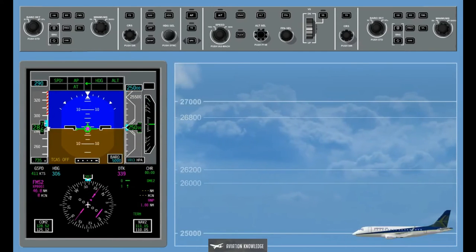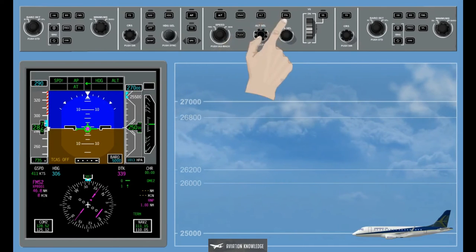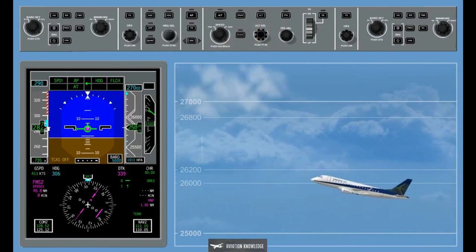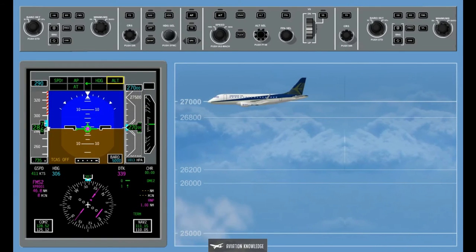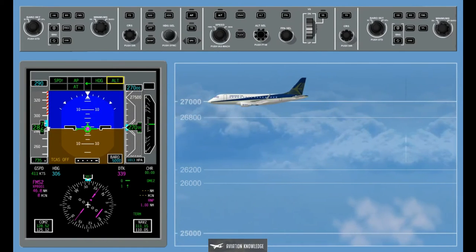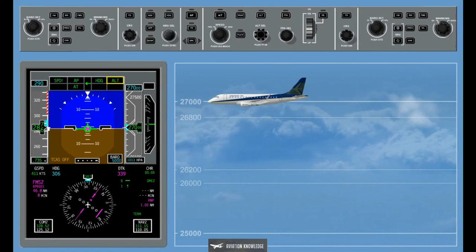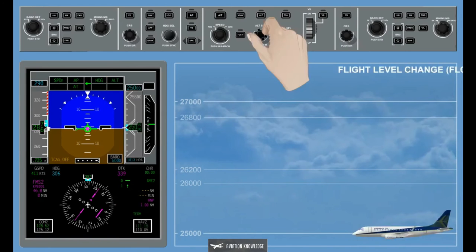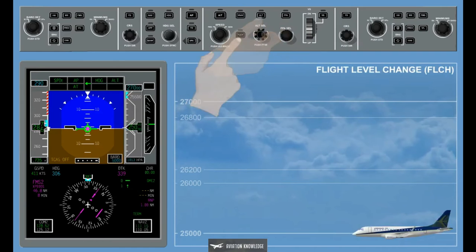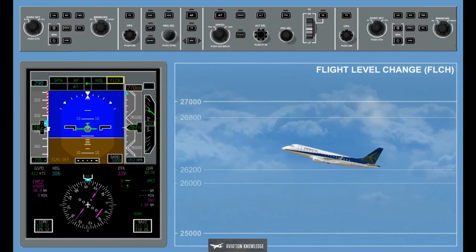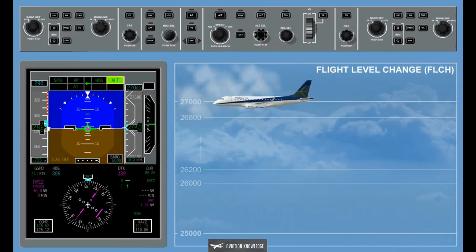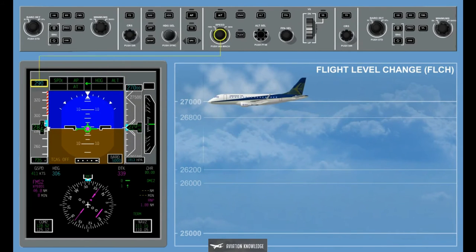The altitude select mode captures and levels off at the selected altitude. The FGCS automatically monitors the aircraft speed, altitude, and vertical speed and performs a transition from the active vertical mode to the altitude select mode to assure a smooth level off at the pre-selected altitude. Flight Level Change, FLCH: The flight level change button on the guidance panel activates the flight level change mode. The flight level change mode provides flight path commands to climb or descend according to the speed selected with the speed selector knob. Flight level change guidance is associated with the flight level change thrust control mode of the thrust management system.